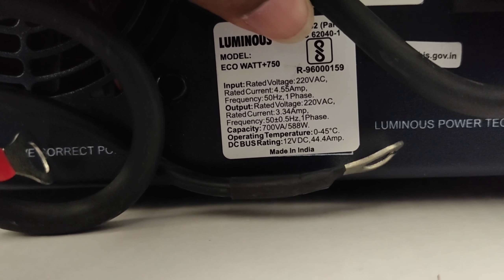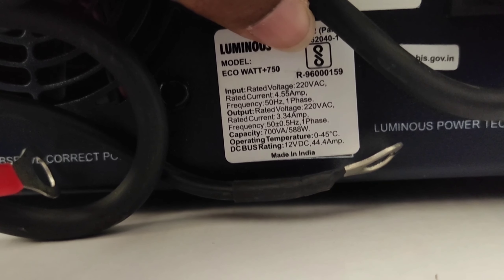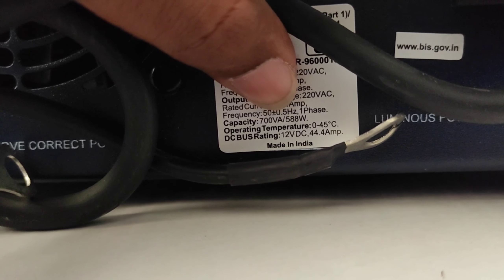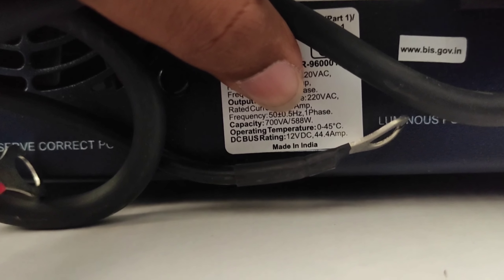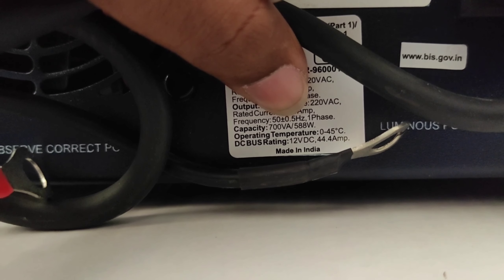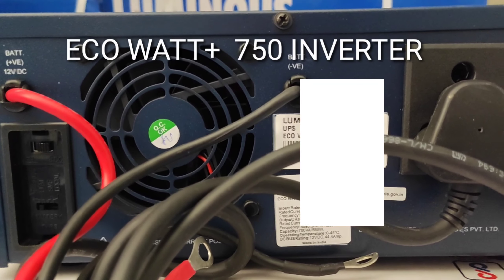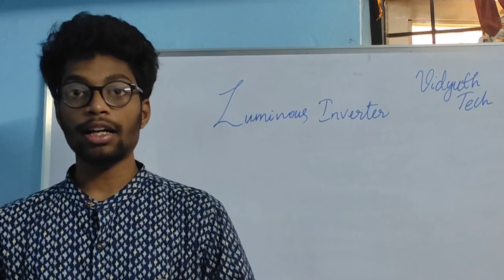Here you can see input 230 volts and 50 hertz. The input rated voltage is 220 volts AC, frequency 50 hertz, and rated current is 4.55 amperes. Frequency is 50 hertz single phase. Capacity is 700 volt ampere. Output rated voltage is 220 volts AC, rated current 3.34 amperes, frequency 50 hertz with tolerance of plus or minus 0.5 hertz, single phase. Capacity is 700 volt ampere, or active power 588 watts. Operating temperature is 0 to 45 degrees centigrade, and DC bus rating is 12 volts DC at 44.4 amperes.